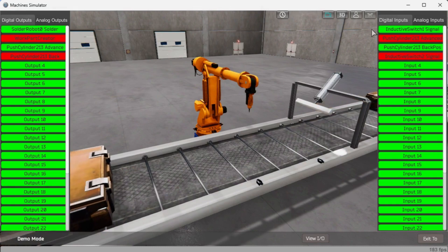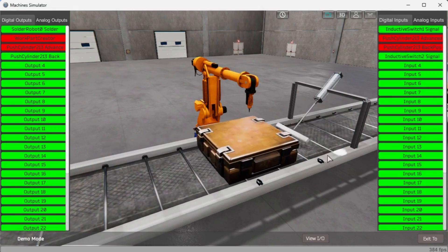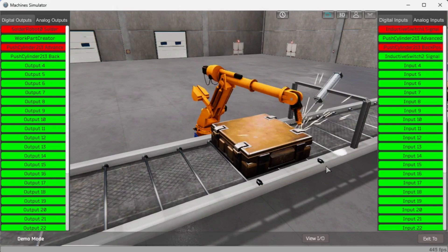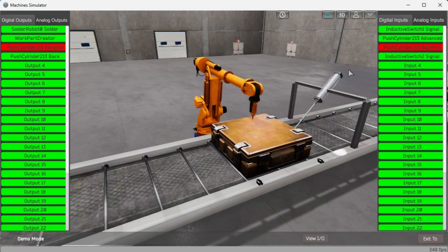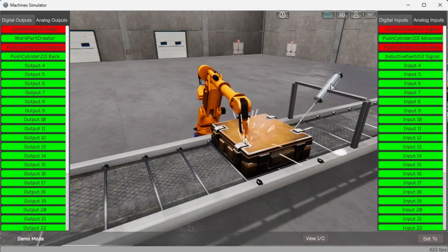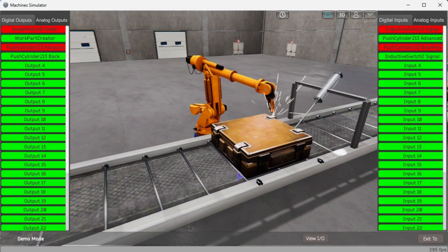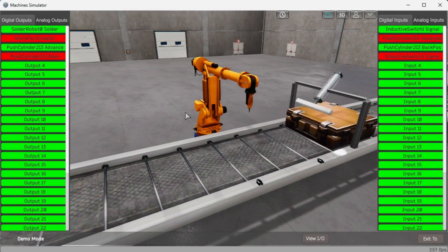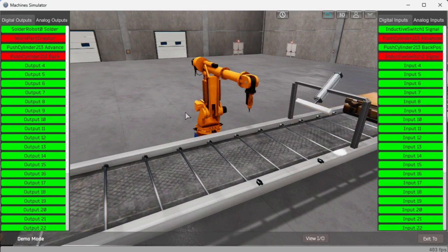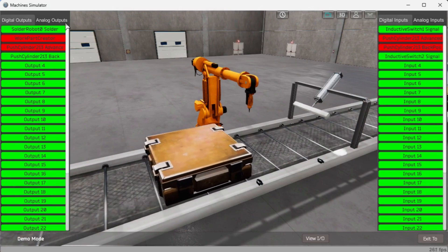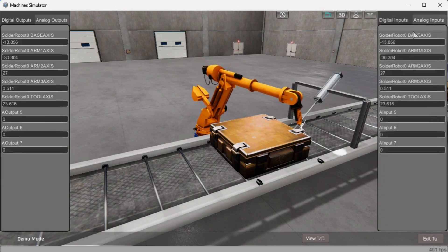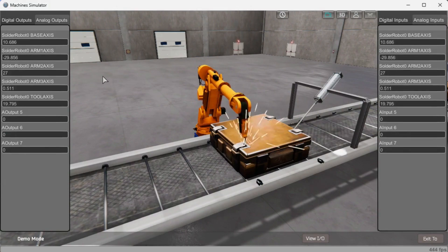The PLC digital inputs: number 1 is inductive switch 1, located closest to the cylinder, which will detect the box position on the conveyor. Number 2 is push cylinder advance — the extend cylinder sensor that determines the position of the cylinder. Then we have push cylinder back, which is the retraction sensor on that same cylinder. And we have inductive switch number 2, which is the first sensor the box will activate as it moves along the conveyor; it is used for positioning of the box. Once we have that inductive switch, we can activate the cylinder to stop the box. We can also select the analog inputs and outputs to see the control of the 5-axis robot. The PLC analog outputs control the position of the robot, and the analog input reports the current robot position.